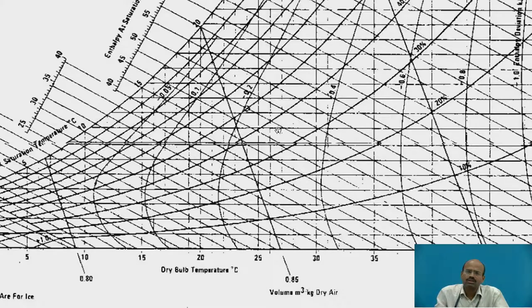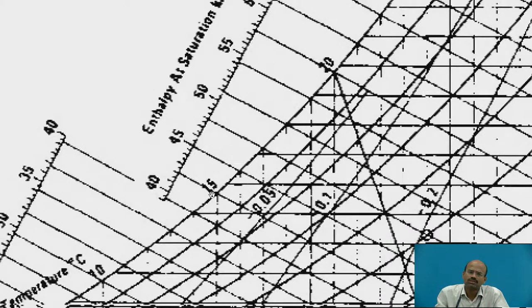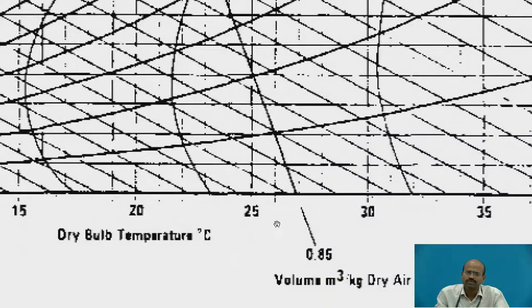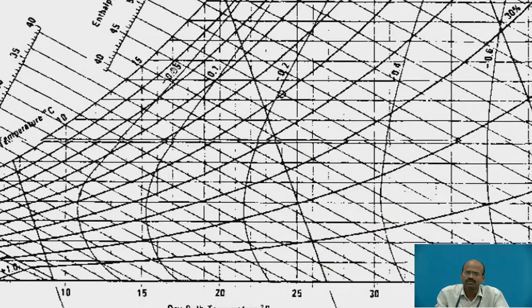Now, psychrometer will give you second property known as WBT, wet bulb temperature. On this outermost curve named as saturation curve, the WBT temperatures are located. This is 15 degrees Celsius, this is 20 degrees Celsius. These inclined lines passing from these temperatures are known as constant WBT lines. Easily we can obtain DBT and WBT temperatures of surrounding air. Then, taking the example of DBT as 25 degrees Celsius and 15 degrees of WBT, the intersection of these two temperatures is this point.